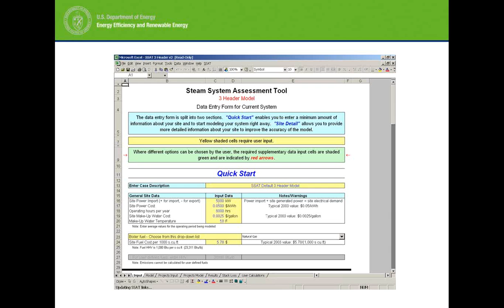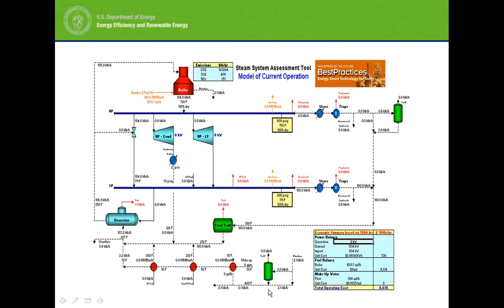Once you've provided the input, it generates a base model line diagram. You've got a boiler, a high pressure header, a low pressure header, a pressure reducing valve, a back pressure turbine, a condensing turbine. Chemical engineers will recognize this symbol as classic for users, or a heat exchanger that takes the steam and makes condensate, steam traps, flash tank, condensate being returned to the condensate tank, users on the low pressure side, all combining. The deaerator model is all built in, taking steam from the low pressure header and doing the water balance. Anything missing comes from makeup water, plus blowdown evaluation and calculations for the flash tank, heat exchangers, and so on.